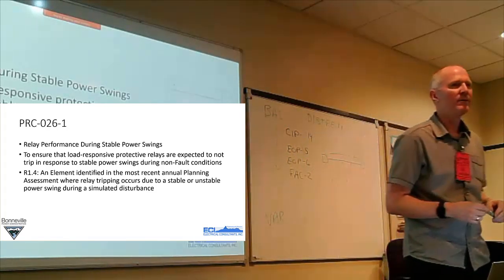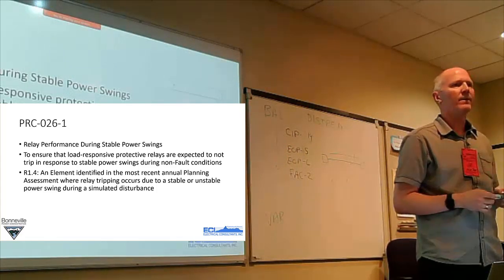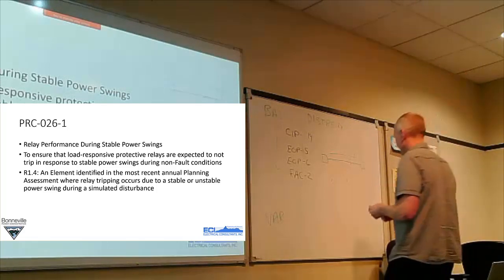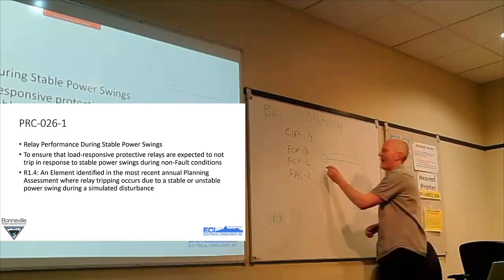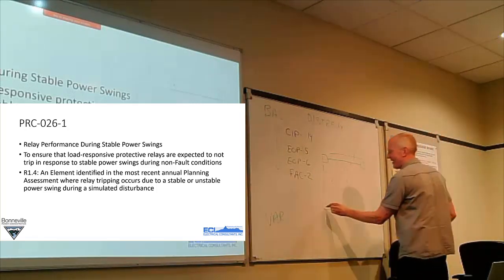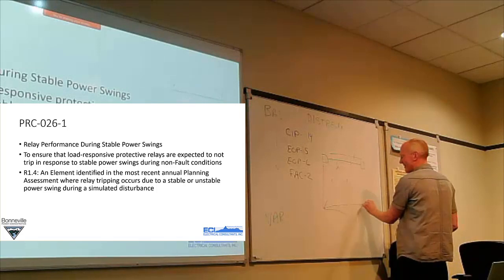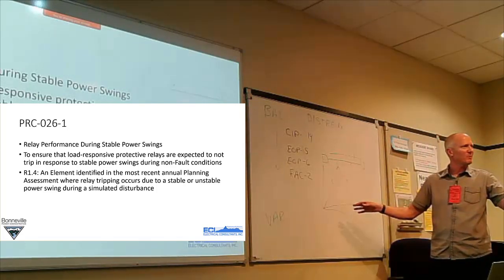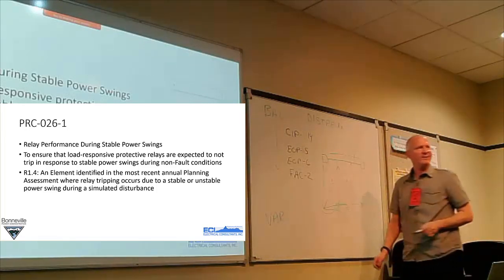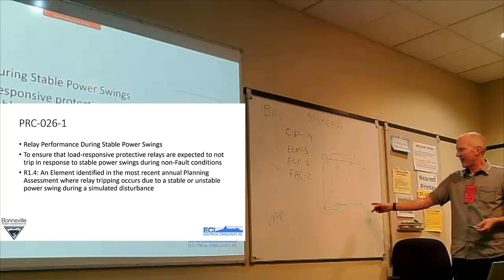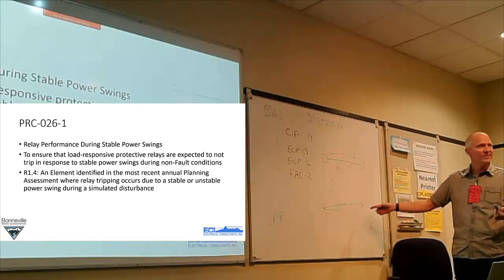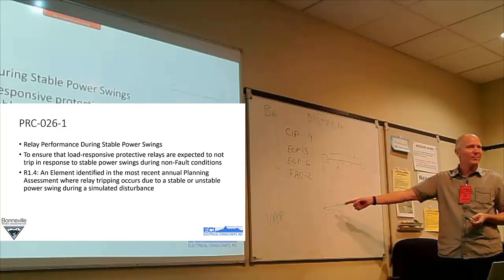I mean, you guys are talking about how big of a power swing you need. So, like, you just keep on cranking up your power swing until you get some relays to trip? Well, I'm not a protection guy, right? But I do have the Blackburn book, just so I can drop the name. And here's the line impedance, and apparently this is load impedance, for you protection people. And if load's big enough, it can wander in here and cause things to trip. So I just thought, well, put a big honking load somewhere, which is kind of like a fault, but it's a load, and see if you can. And I did get one to go into the zone.